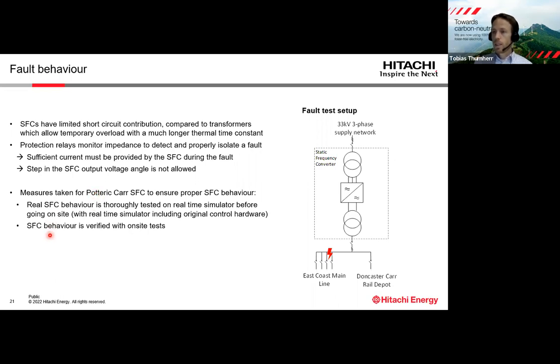Measures that have been taken for the Potteric Carr SFC were that the SFC behavior was thoroughly tested on the real-time simulator before going on site, including this fault behavior. And the SFC behavior is also verified with on-site tests. Real tests were done on site, applying a short circuit and measuring or observing the SFC reaction to that.